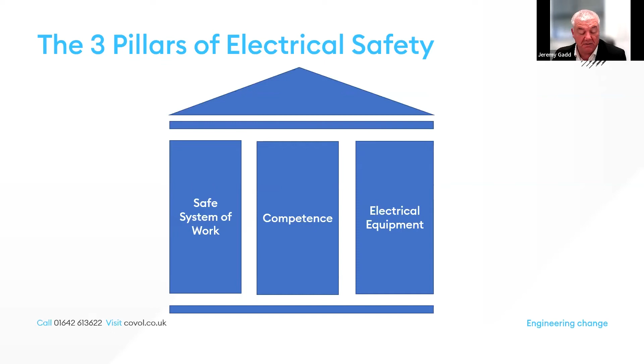The Management of Health and Safety at Work regulations makes a clear statement on assessing the risks to employees and anyone not employed that may be in or working or near work being carried out. As we all know, risk is a result of likelihood versus severity. So when we take an example of a typical cycle here, showing the process of risk assessment, when applied to electrical safety, more specifically in arc flash, there are a number of factors that influence the likelihood of harm, plus a similar number of factors that influence the severity, shown on the right-hand side.